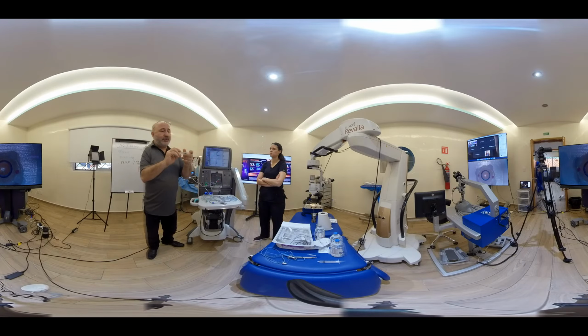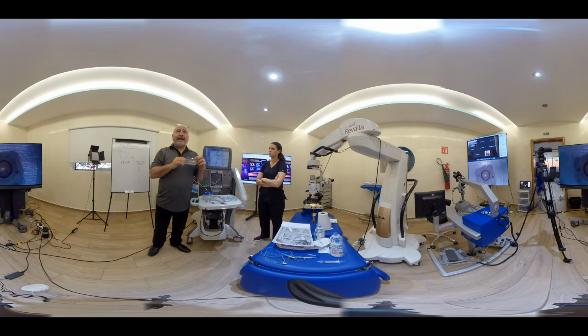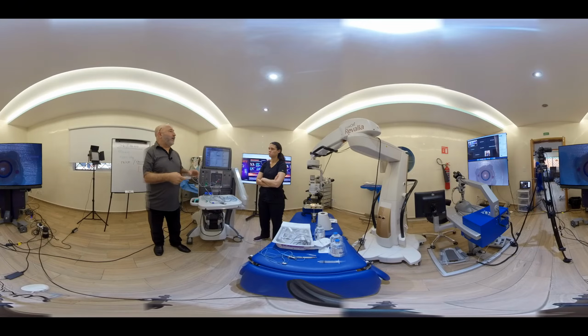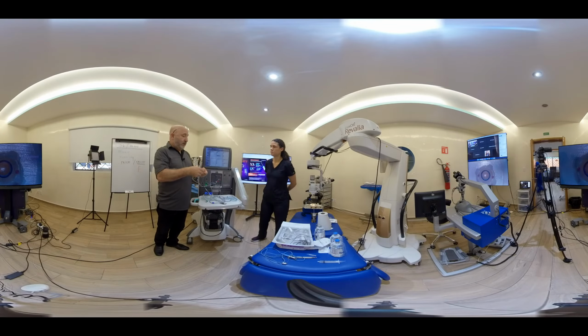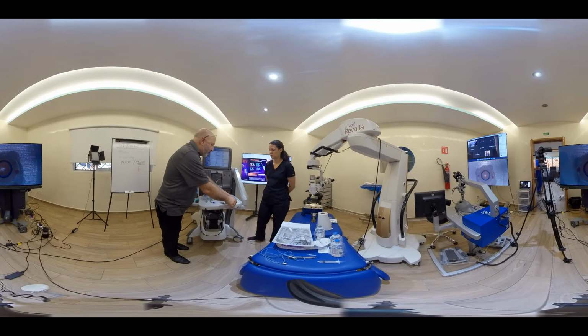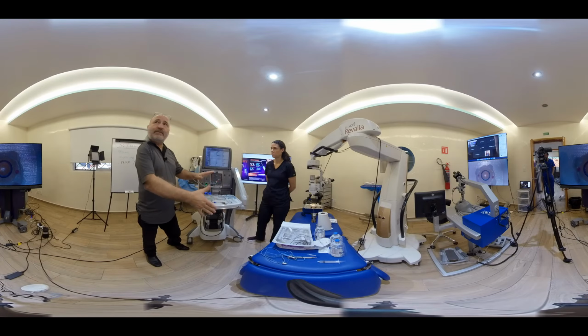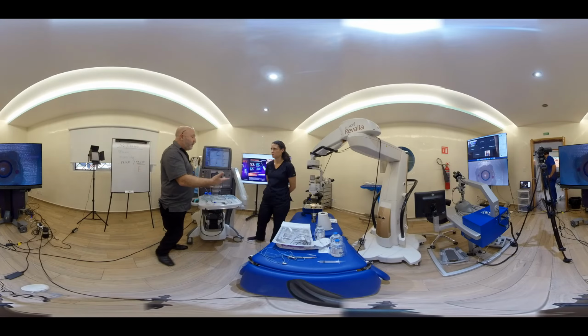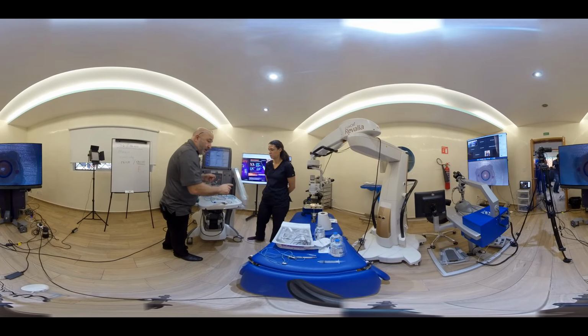Then we've got our calibration tray. And on our calibration tray, we've got the word Alcon on the side that you should open. So hold the rest and then peel it back so it doesn't bounce. So many people just leave it like that and let it bounce. If it bounces, it creates vibrations and it then gets a noisy calibration failure of a prime. So especially if you put it here and they haven't got it on a firm surface and the floor's a bit shaky and you're walking around, that causes that error.